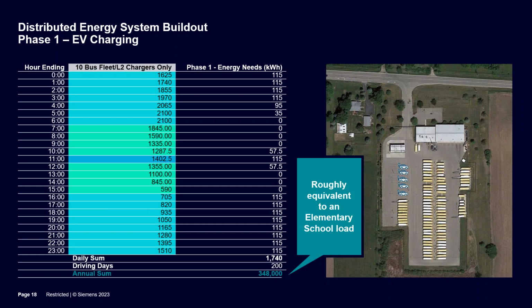This particular operation of adding 10 buses to the fleet with level 2 chargers only had an annual power requirement of about 348,000 kilowatt hours, equivalent to a typical elementary school. This is a very rural location, as you can see from the Google Earth image, and they were fortunate that the grid was able to supply enough power for those 10 buses and level 2 chargers without much grid upgrade, which was extraordinary. They were able to do this relatively inexpensively with just level 2 chargers on specifically designed routes that would match the power requirements.